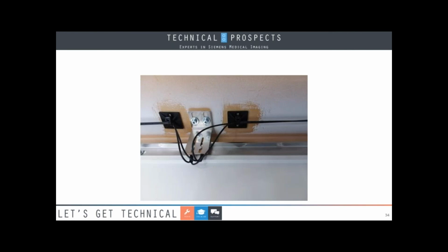When we first started, I talked about a table issue an operator complained about. Most of them, you walk in and you can't duplicate the issue. One thing I started doing later on was adding weight to the tables, because I started realizing that these tables can hold up to 650 pounds, which is a fairly decent sized person. And it made a huge difference to how the table was. So I didn't do it at the start, but later on I started when they would give me, well, we got a noise or something. And one time I actually put 3 operators on the table, and the third operator, yeah, I heard my noise. So maybe then you'll hear the noise, see it vibrate or skip.